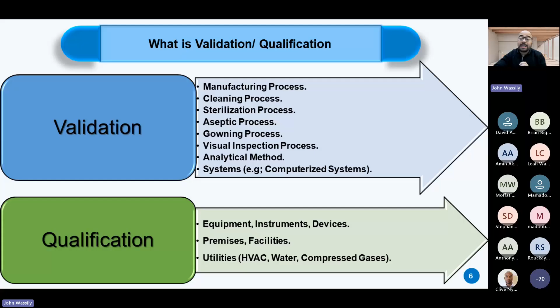So, for example, by saying cleaning process verification or cleaning process validation here, I mean making sure that the cleaning process is actually giving us an equipment or a facility that is really clean. And by saying, for example, sterilizer autoclave qualification, as mentioned, is to make sure that the autoclave will give me a product sterile and free from any microorganism. Applying this on any other equipment, like the filling machine that will be used in filling the vaccine products, will be about making sure that the filling machine will finally give me the nominal volume that is expected in my vaccine product in a consistent manner, okay?